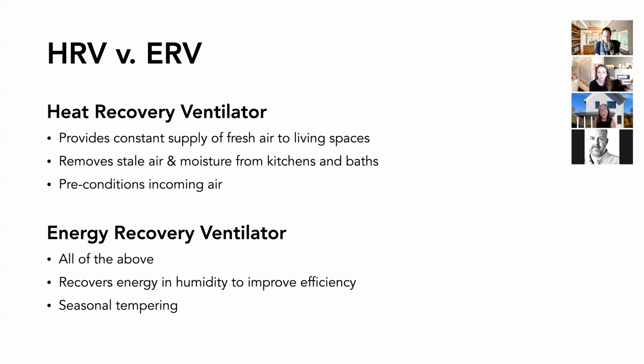The energy recovery ventilator does all of the same things. Its core is typically a filter material, almost like a paper. It can handle humidity. And so when air is coming into the house in the winter, we typically have a warmer and drier interior air. It can bring in some humidity to our air, and it lets the humidity stay. So it actually can help with static in the wintertime, which we often experience in code-built homes. It also, in the summertime, likewise can extract humidity from our interior air and not let it pass through from the outside. So we do have that seasonal tempering with energy recovery ventilators.